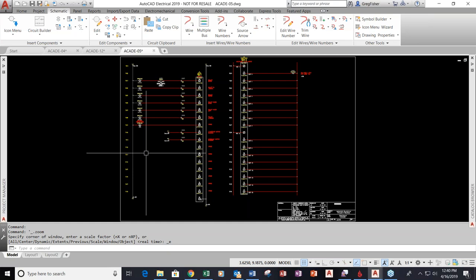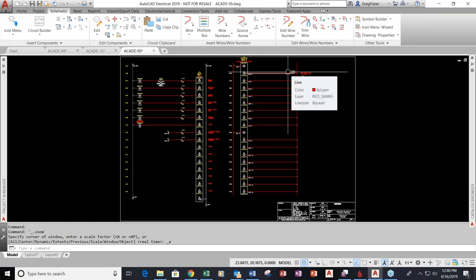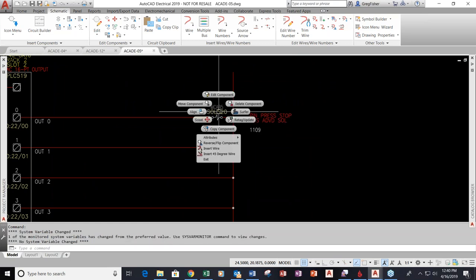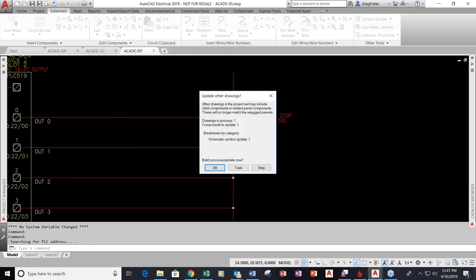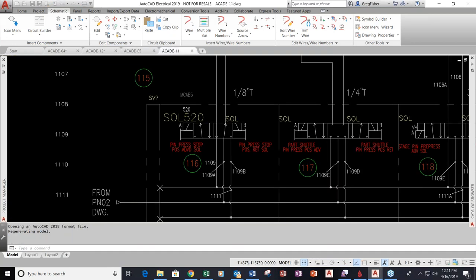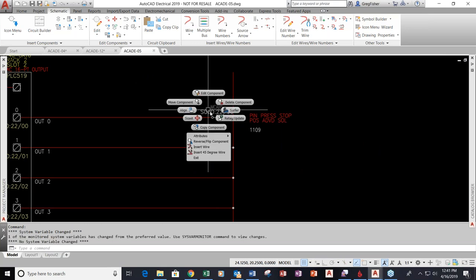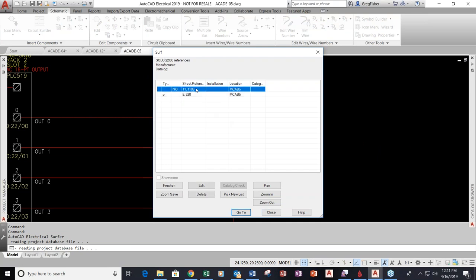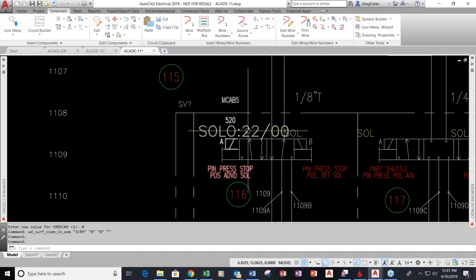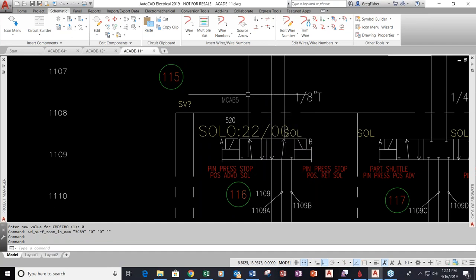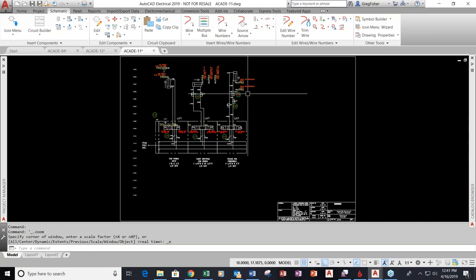How difficult would that task have been using regular AutoCAD? In my pneumatic drawing, everything would be manual. Let's say I change the tag — I'll use the PLC address on the tag, so now it's SOL O colon 2200 instead of using the sheet line reference. Update other drawings — absolutely. So instead of that being SOL 520, it changed to the PLC address and automatically updated the pneumatic symbol as well. The main point is: you make a change to one, the other one updates automatically. That would be very difficult to do inside of regular AutoCAD.